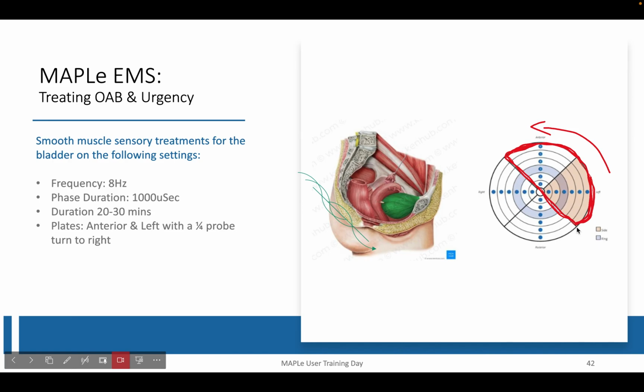There is also a setting for treating overactive bladder and bladder urgency. Here we would choose the 6 electrodes of the anterior plate and the 6 electrodes of the left plate, but we would rotate the probe to the left by an eighth turn. So it wouldn't be a full quarter turn, just an eighth turn. So then that would be treating the bladder in particular, and here we are treating smooth muscle sensory nerves.